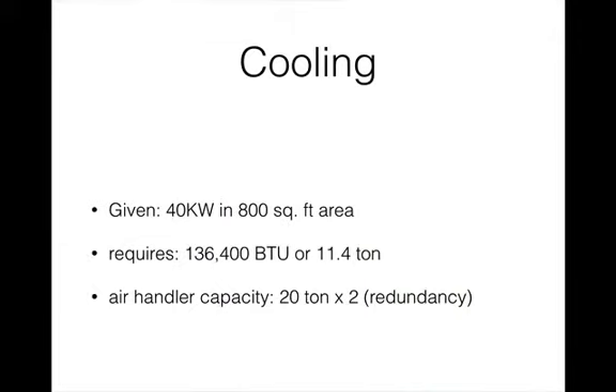Given the 600 to 800 square foot space and full load of 40 kilowatt, the cooling requirement is about 11.4 tons. The Word document has more information and detailed calculation on this. Each air handler has about 20-ton capacity, so a single air handler should be sufficient for the entire cooling. However, as redundancy and as a backup, I added a second air handler.